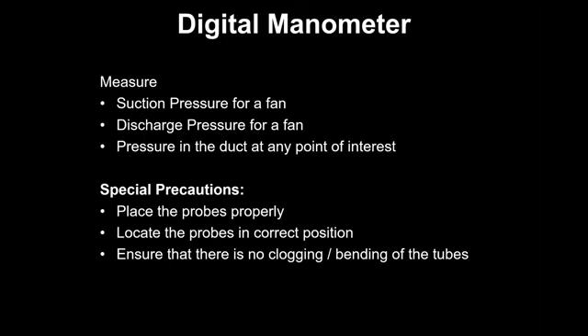It is also used along with the pitot tube, but that is a different range. With pitot tube, the delta P is very small. It may be 10 or 15 kind of thing. So we have a small digital manometer, as I said, because of that accuracy range and all. We have a specific separate manometer only for pitot tube, having very small range and higher accuracy. And for fan, we have a different manometer.